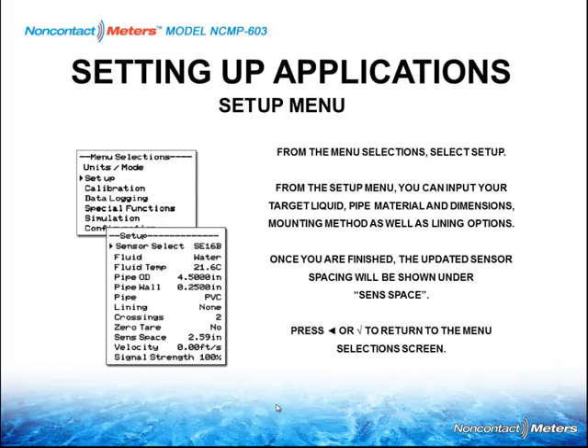We give you an ANSI pipe chart book. Please use it. When you say you've got a 4-inch pipe, you don't punch in 4 inches. You go to the pipe chart book, or you take a tape measure or string and wrap it around the pipe, divide it by pi, 3.14, the only thing I remember from high school, and you'll have your pipe OD. If you have the wrong OD, it'll give you the wrong spacing. Pipe wall thickness, we have thickness gauges that you can buy or rent, but in most cases it's not necessary. If you use the pipe chart book, you're usually just fine.